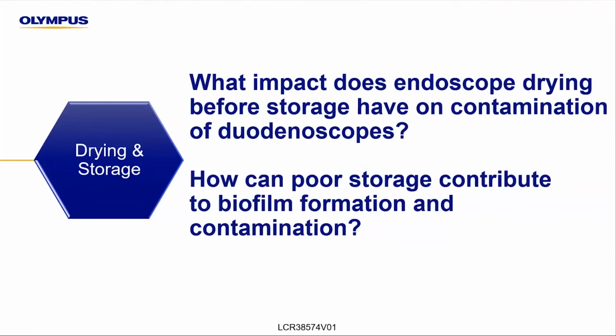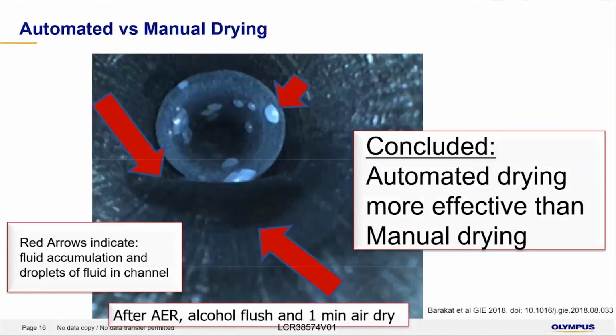What impact does endoscope drying before placing scopes in storage have on contamination? And in addition to that, how do you think poor storage conditions can contribute to contamination of the scope and biofilm formation? Okay, so I think it was interesting to look at this picture, because Thaker in 2018 did a survey of 249 endoscopy sites, and they found that less than half of the sites were using forced air to dry the endoscope channels prior to storage.